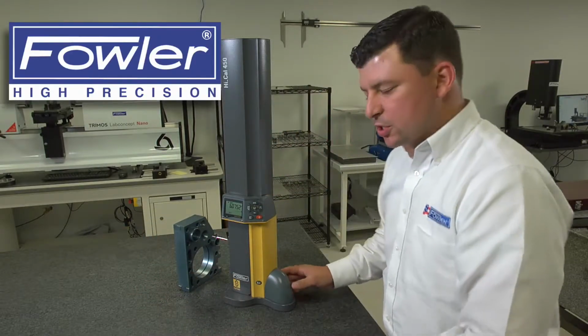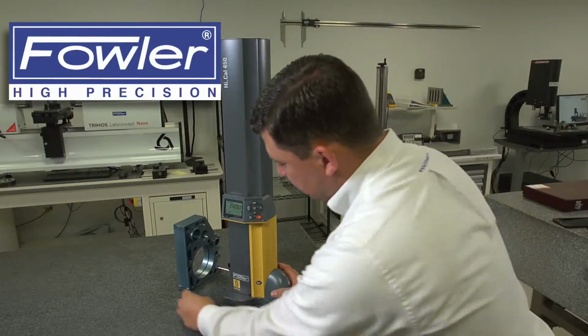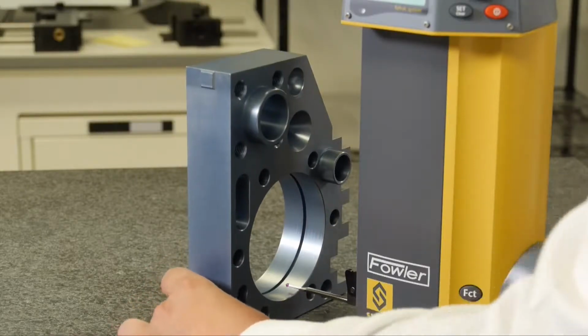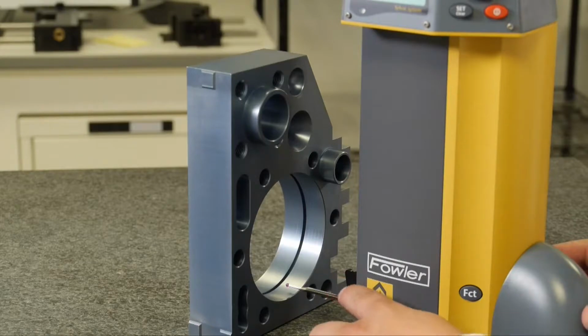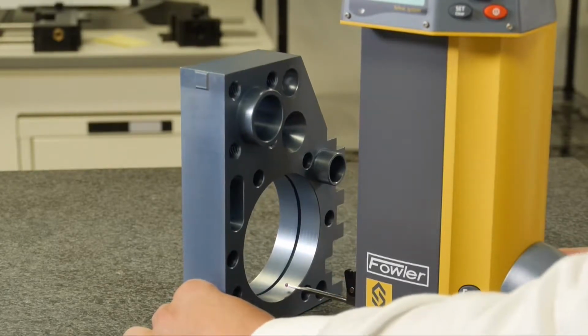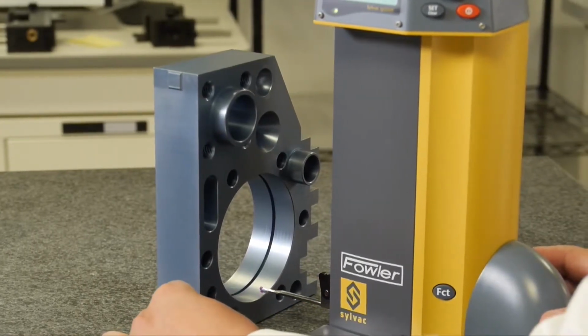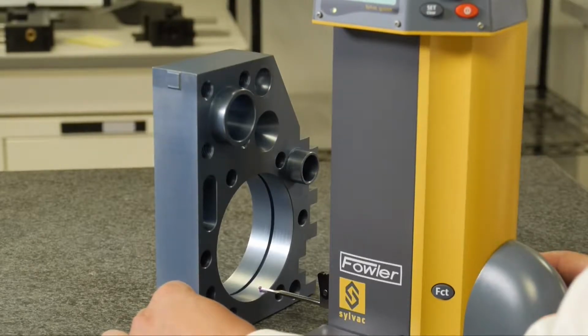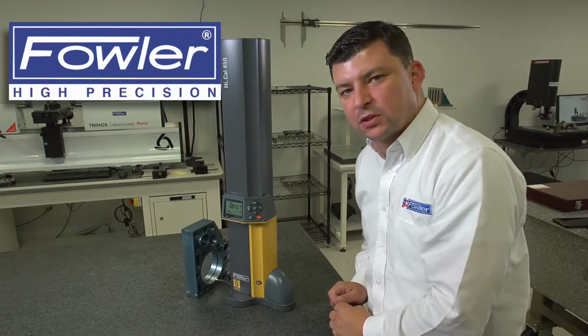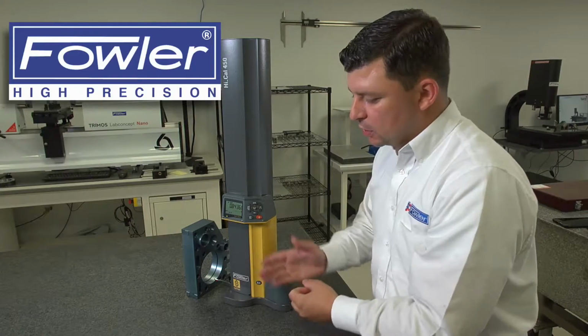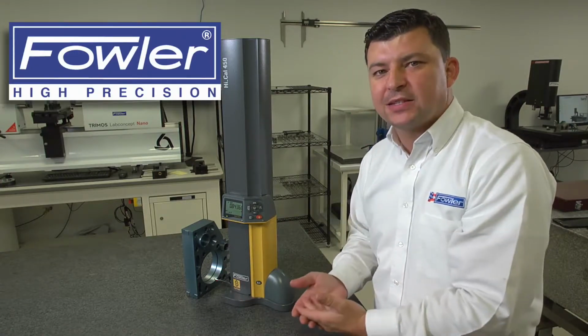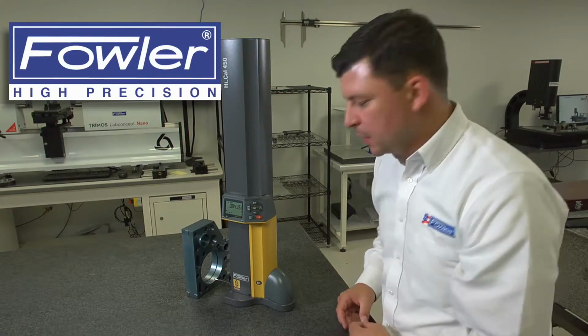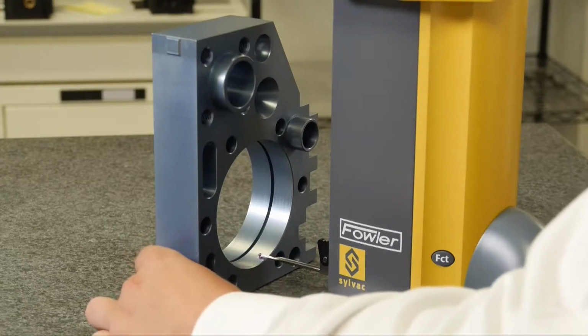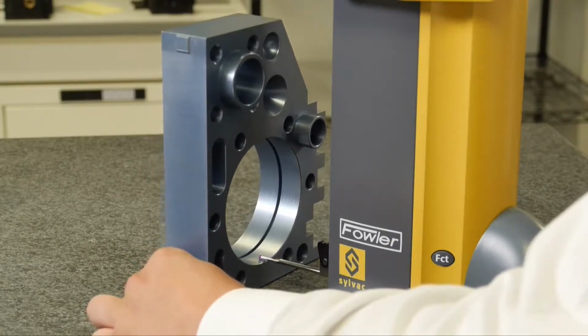To show you this operation, we'll drive into our bore. In diameter mode, we're going to be slightly off center from our reversal point. We will engage our probe. At this point, when our probe is engaged, there's a constant measuring force that's going to sit down on that probe so we can tram through that surface with the probe maintaining contact through the contours of the bore. So my probe is engaged. I can sweep through that bore.